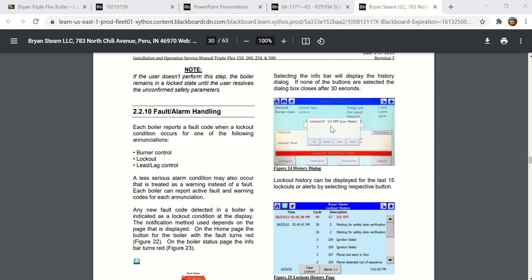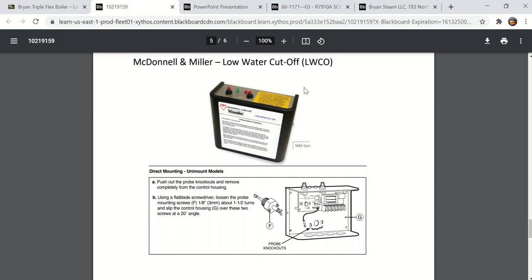But if you had this alarm, ILK off, low water, the first thing you would want to do is look at your low water cutoff. You'd open up the door, you find this low water cutoff, you'd look for a green light here, means it's powered up. A red light here means it's in alarm. Push the reset button there.